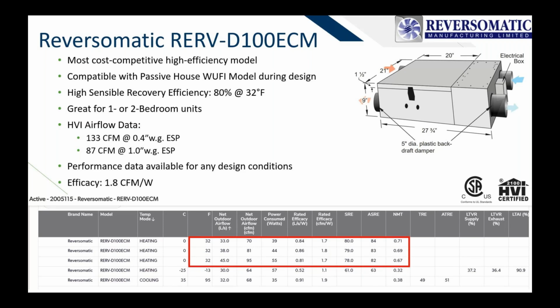The airflow is a little bit lower at 133 CFM at 0.4 inches static pressure and 87 CFM at 1 inch. So it would be good for a 1 or 2 bedroom unit, whereas the previous examples would have been really good for even a 3 bedroom unit. So it's worth noting too that you could do a hybrid schedule for your design where you use both and make it really cost competitive. That way you for sure would see these in the submittal phase.